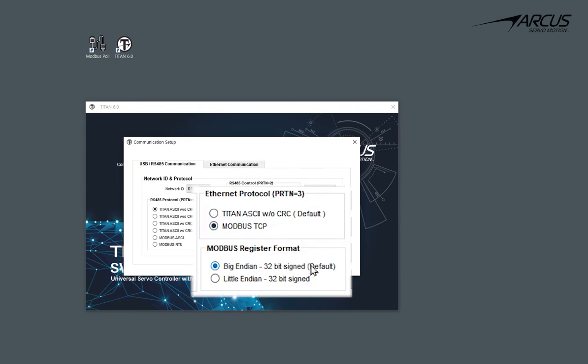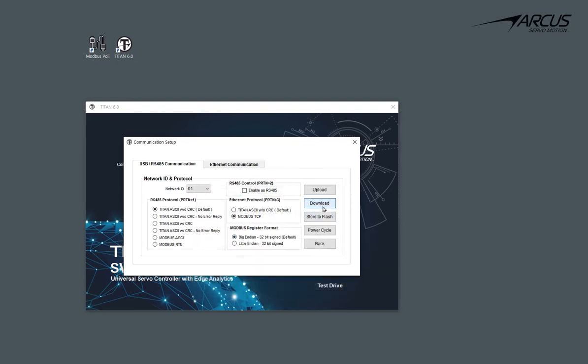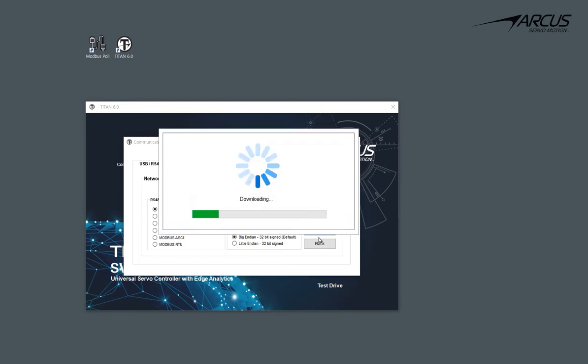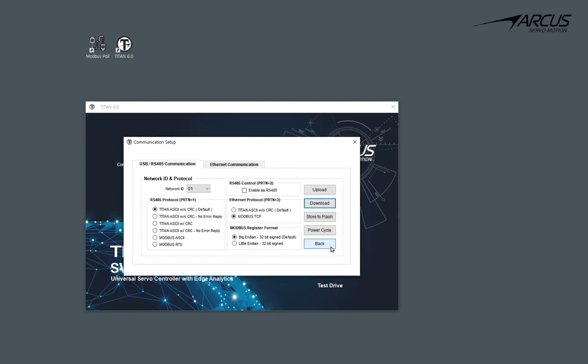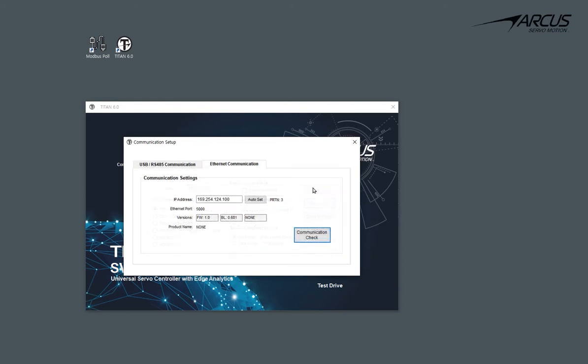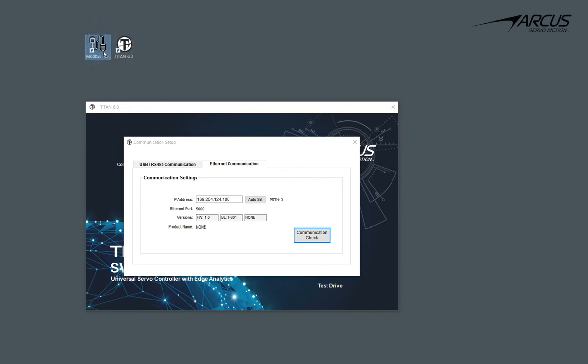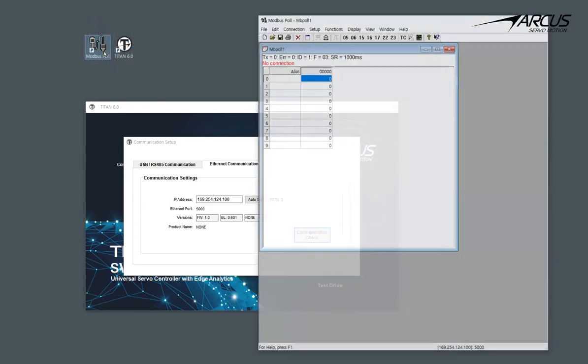Let's also set the 32-bit register format as the signed Big Endian. Download the new protocol. Now the Ethernet should be communicating in the Modbus TCP protocol. For testing the Modbus communication, we will use the free Modbus Master Test program called Modbus Poll Program.